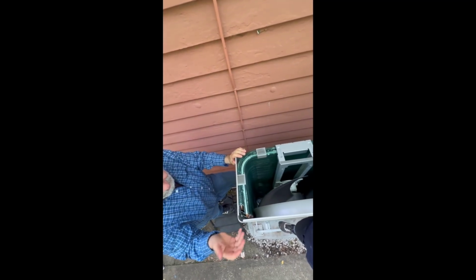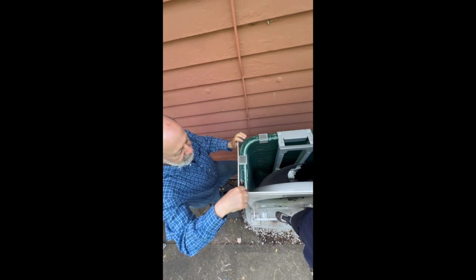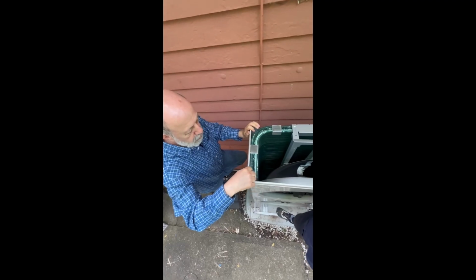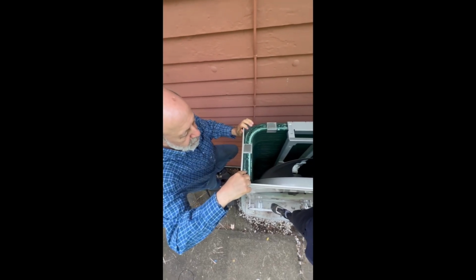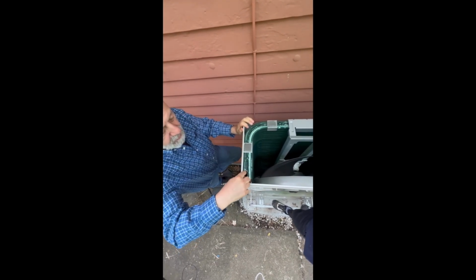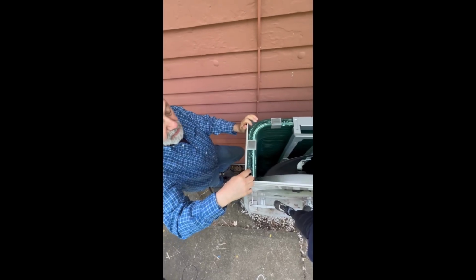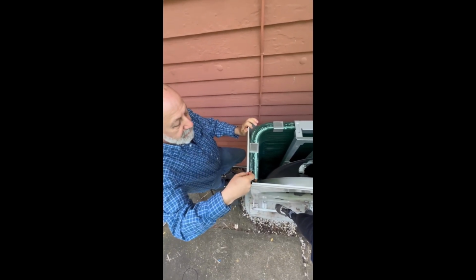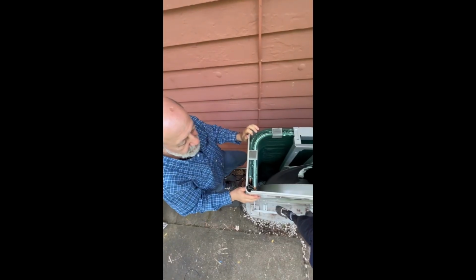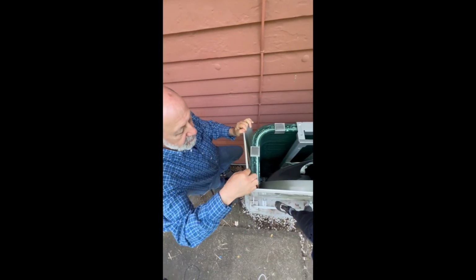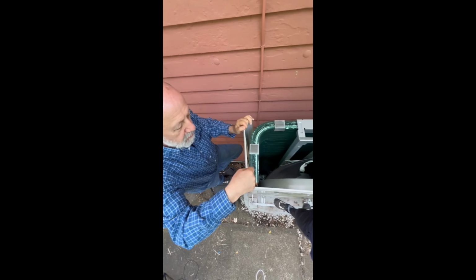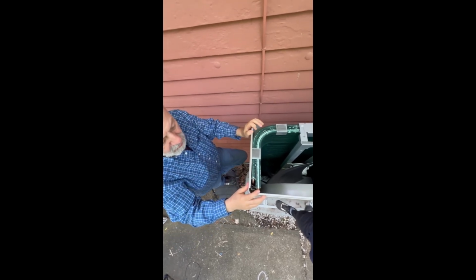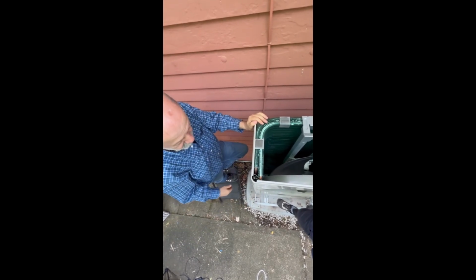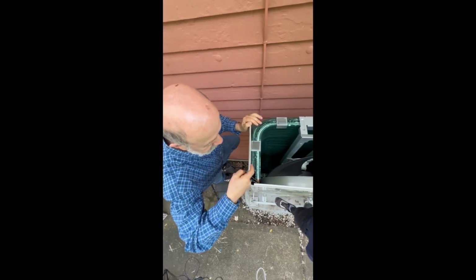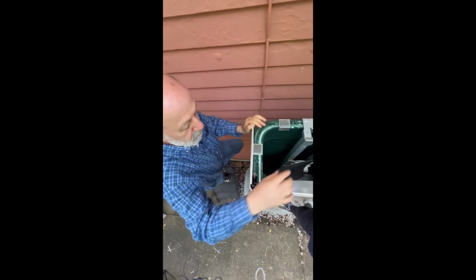Well, this is the heat exchanger. The largest air bypass was at this end. There is no tube sheet. There's a tiny tube sheet here, which is a piece of steel anchoring the end of the heat exchanger, but it's not fastened to this side panel. So air gets in right up through here, and we measured about a quarter of an inch gap all the way down, over 50 inches. And it gets in through here and goes through the fan.